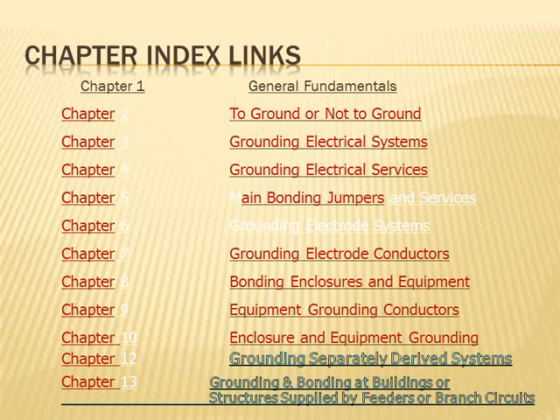So here's your transformer that's grounded. Here's your service that has the neutral, also grounding the system again at the service. That's what the main bonding jumper is. And then the equipment, the frames and boxes housing all the electrical system, has to be grounded also. So you create your own grounding electrode system and you ground anything metallic in your building. Anything metallic in your building.